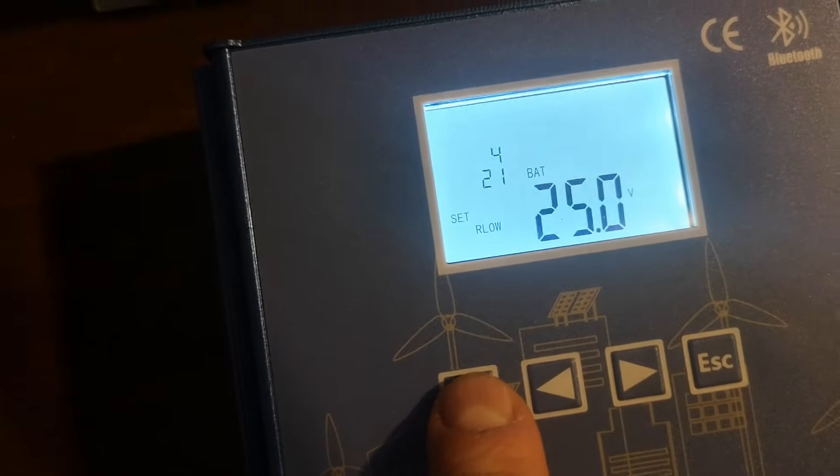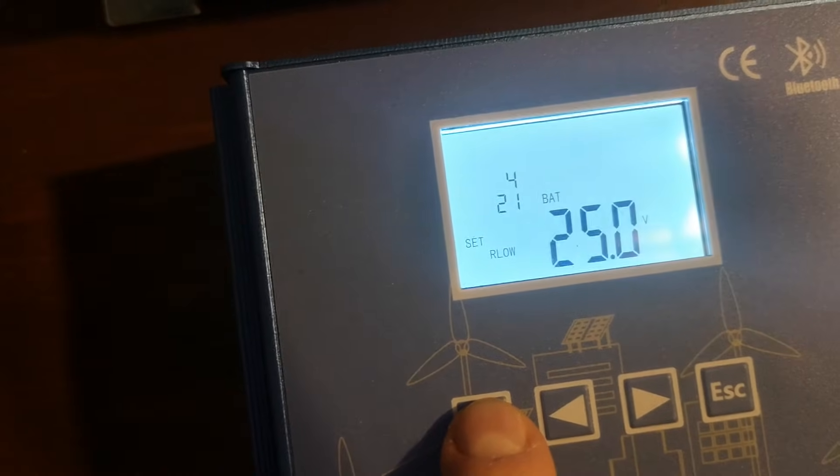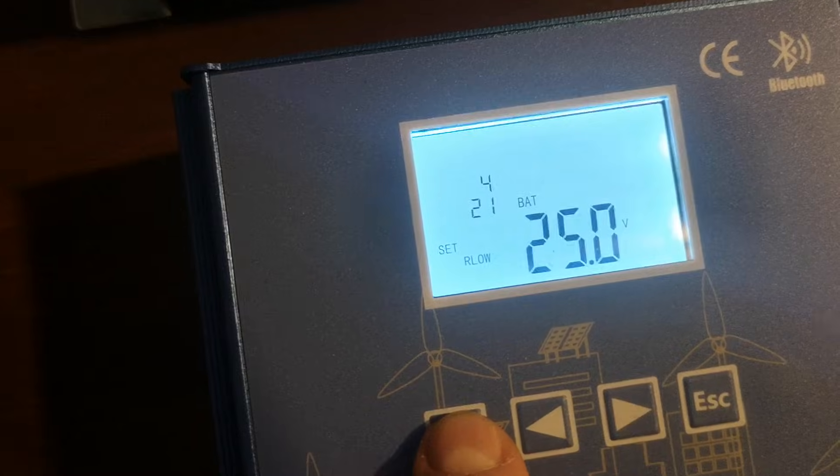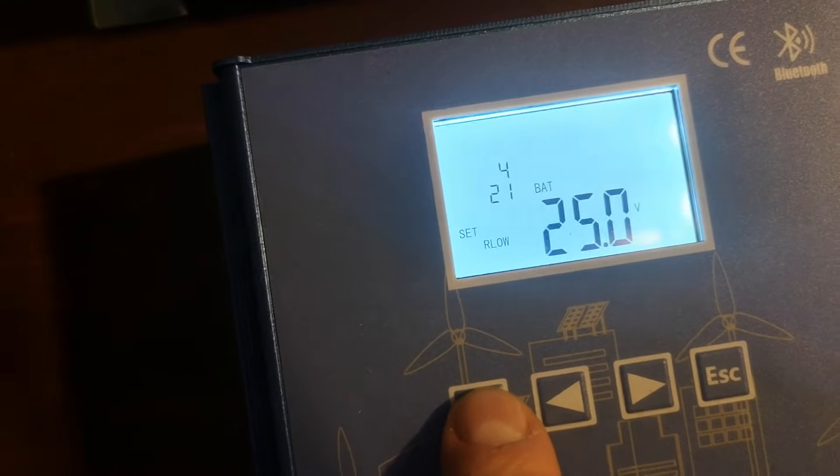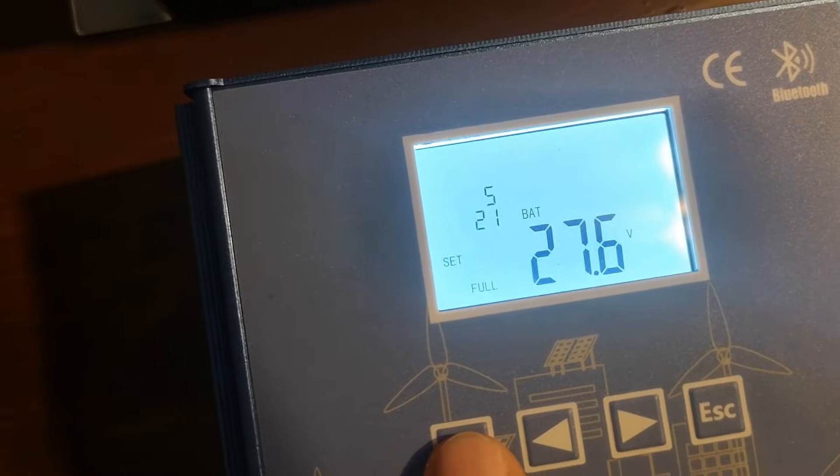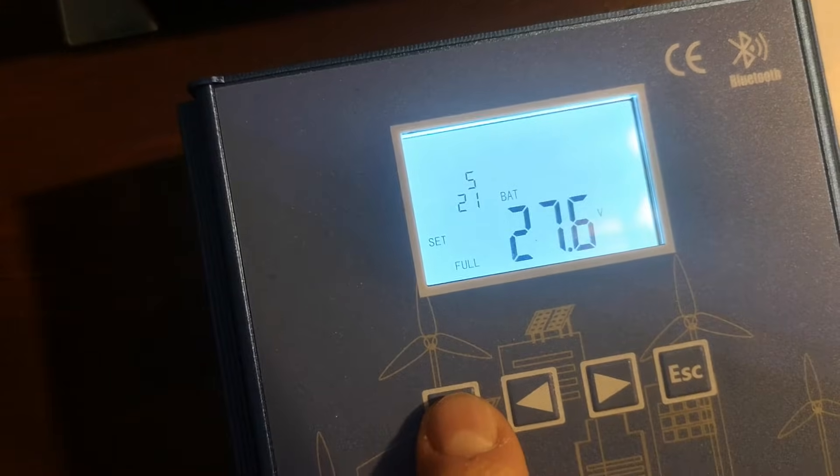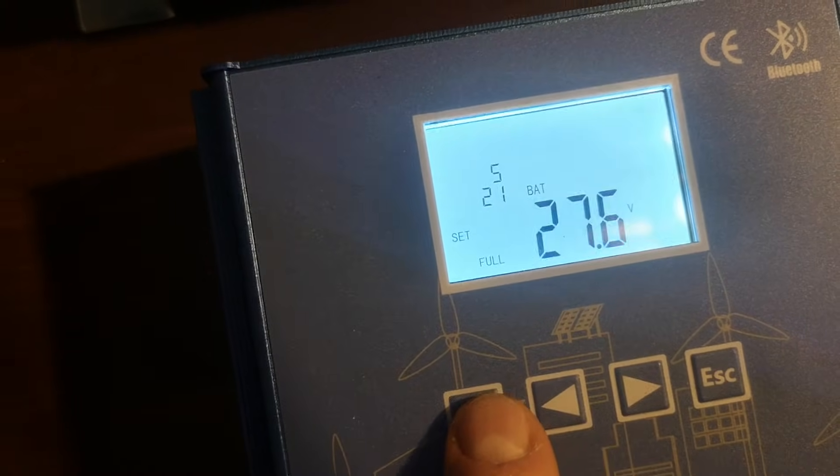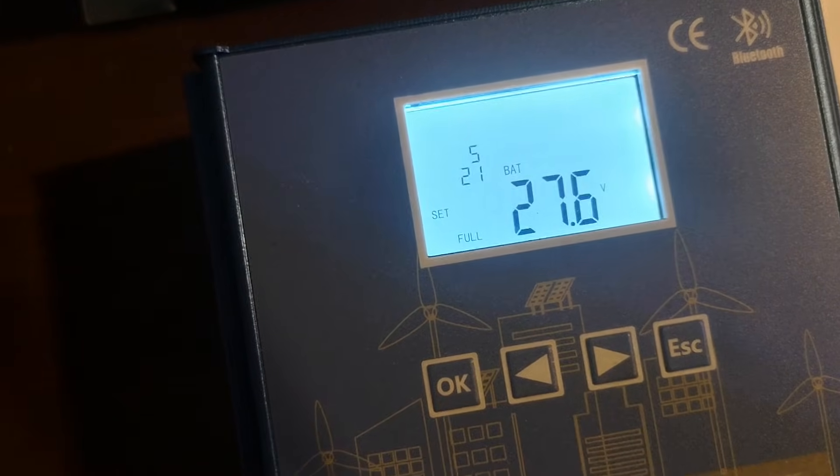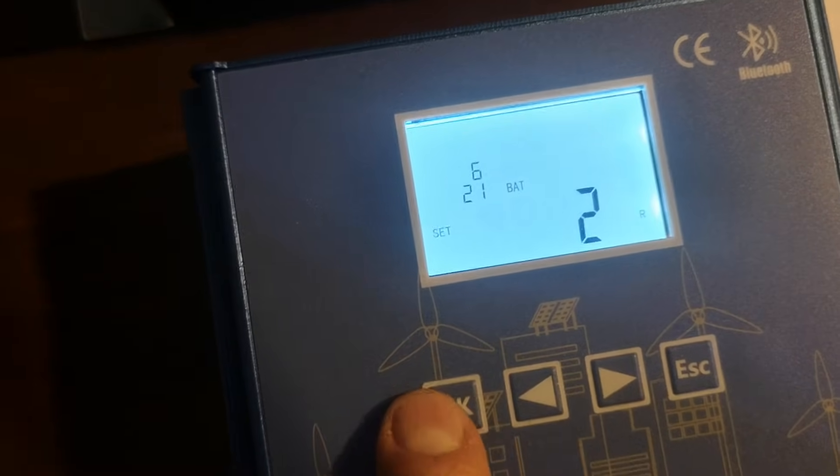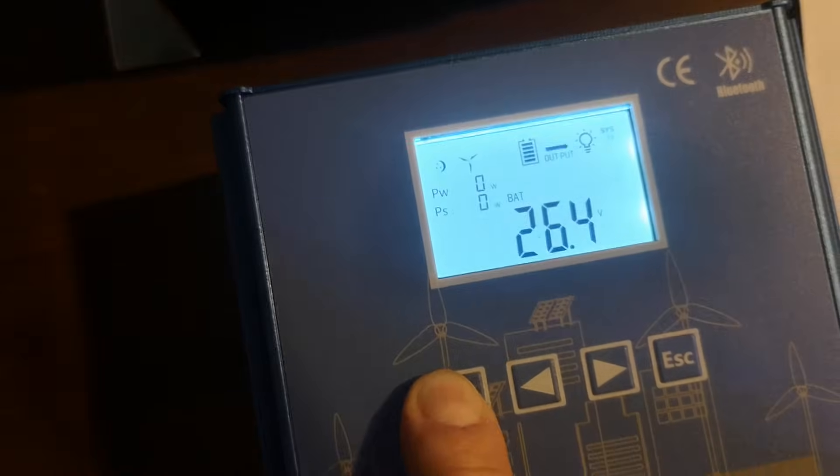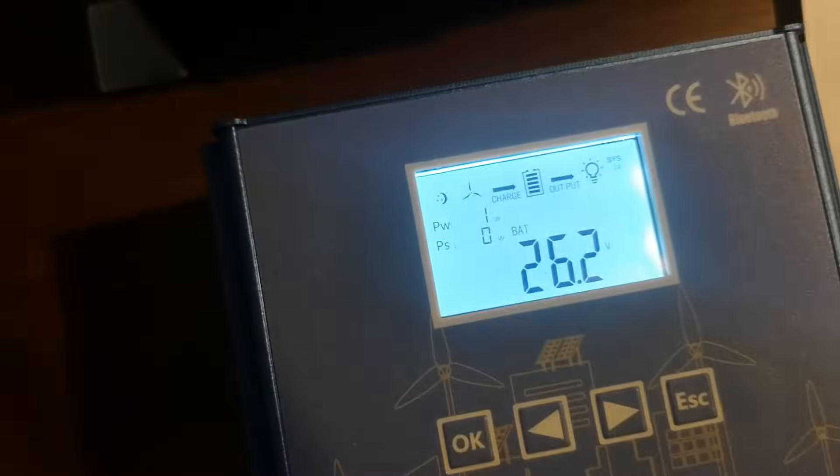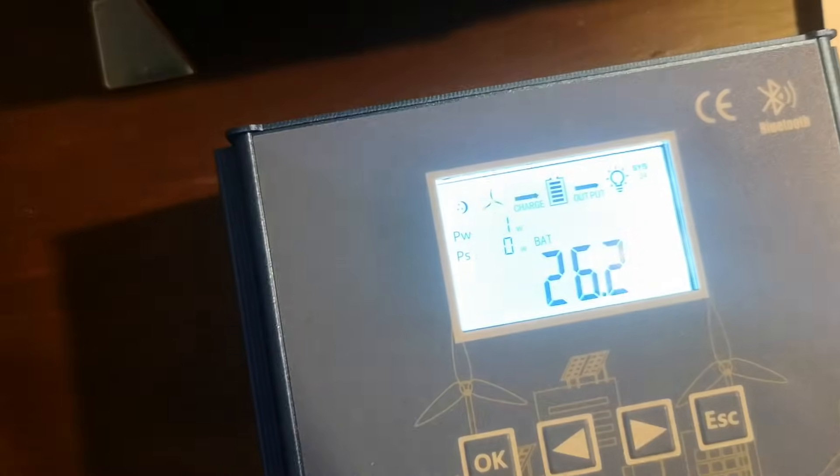Option number four is the over discharge recovery voltage, so when the load is enabled again after battery gains some power from the sun or wind. And very important thing, option number five is the over charge protection voltage. Why this setting number five is so important? Well, basically if I spin the wind turbine now... If you want to save settings just press OK, hold, and it will be saved.